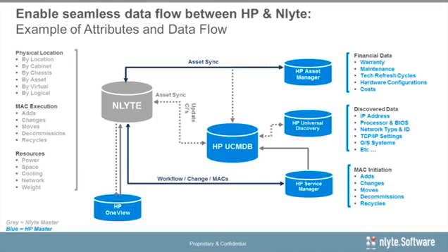they get the benefits and the understanding of the physical world, and as that physical world changes, and the locations of things. We also, and it's worth noting, we also tie into the server-based technology. So in OneView, we can start bringing back the real-time usage and the power usage of those servers and those devices, and add that into the model. So now we know the physical power and usage within the data center from an infrastructure point of view. We know the power usage from a server point of view. We can extract the power usage of the server from infrastructure to give you your remaining capacity in real time.